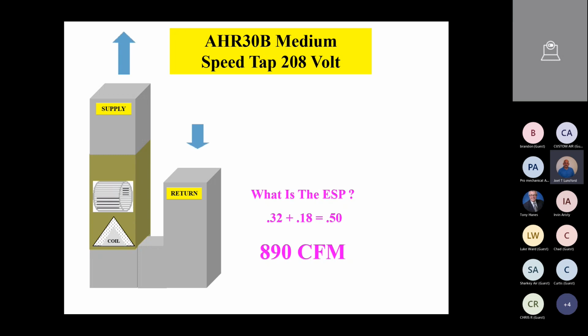Now I hate saying rules of thumb, because it can vary so much by manufacturer. They have an N coil, a W coil, an M coil, an A coil, whatever, a slab coil. However, most manufacturers will tell you that their coil, clean and wet, and let me stress that, clean and wet, will typically have about 0.2 inches of water column static pressure. So if you absolutely can't get anyplace else, go ahead and poke a hole above the coil in the cabinet, read what the fan is sucking, and then add about 0.2 on top of that for a wet coil.